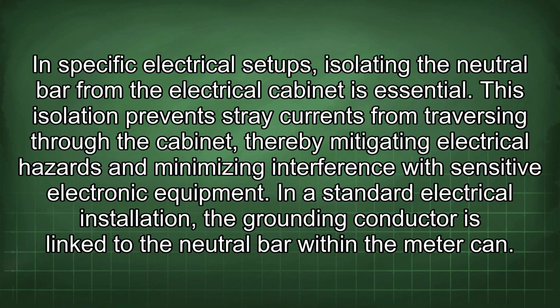In specific electrical setups, isolating the neutral bar from the electrical cabinet is essential. This isolation prevents stray currents from traversing through the cabinet, thereby mitigating electrical hazards and minimizing interference with sensitive electronic equipment. In a standard electrical installation, the grounding conductor is linked to the neutral bar within the meter can.